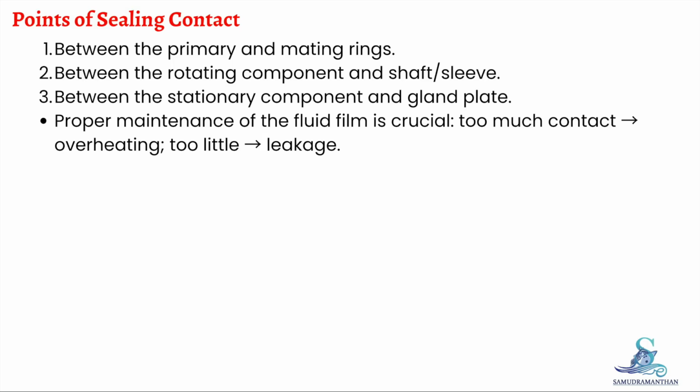The seal's reliability depends on maintaining a thin liquid film at the primary contact points. Too much contact can overheat the materials, while too little can cause high leakage rates.